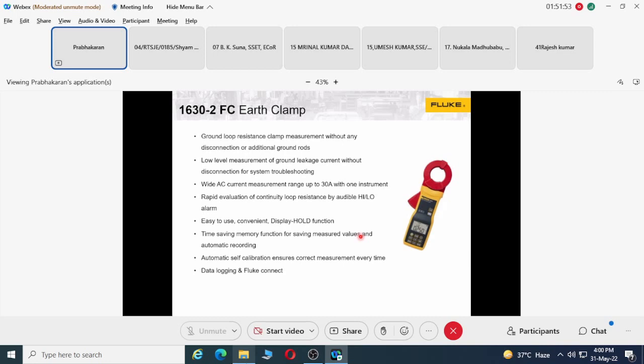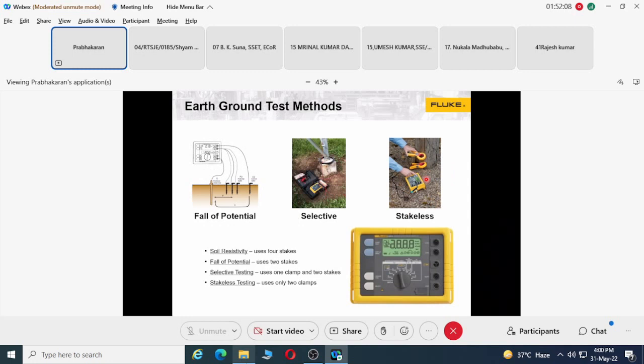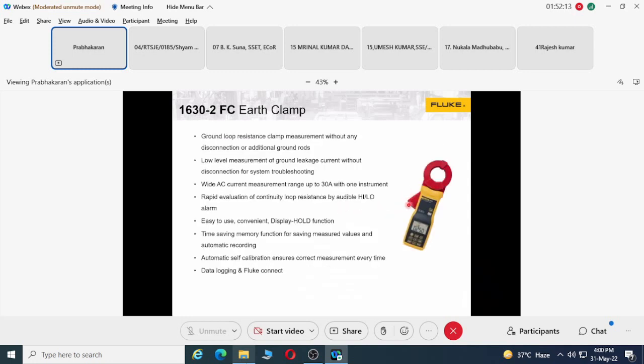Another method of earth leakage testing is the ground loop resistance clamps. This clamp also has 2 portions, one is a sourcing clamp and the measuring clamp, and it works exactly like the stakeless method - 2 clamps. But this has a very small footprint, and you will be able to just clamp on to any of those earth wires and find out what is the kind of leakage or earth resistance. All those things you will be able to find out.